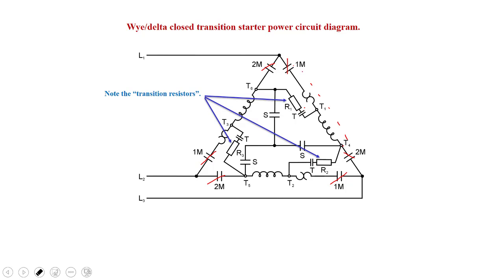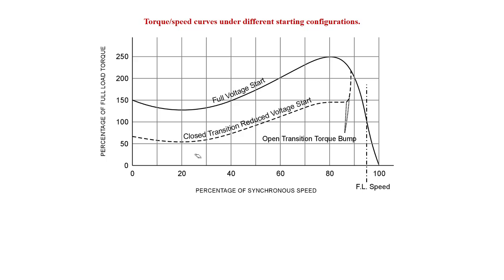So I'm not sure if this closed transition diagram is in your ILM, but we have closed transition starters for Y delta as well. And for those you would need transition resistors and a fourth contactor. So once again, the torque bump is reduced because we have a closed transition. We would just be trucking along, and instead of it dropping down like it would in an open and then shooting all the way back up, it's just going to do the one bump up to when full voltage is applied to it, and the motor will keep accelerating, and then we will operate it at full load somewhere in that area right there. Oh, there's full load speed right here, that line.